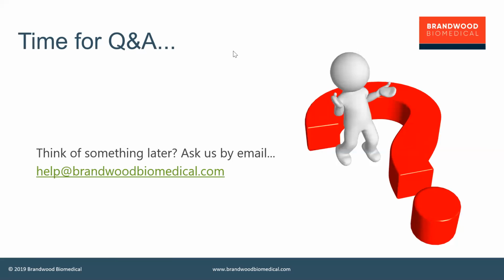We've got a question from Emmett. If you have a well-established product with historical complaint codes, should you correlate those with harms in the FMEA? Very good question. With historical, yes, I think you should. Undoubtedly. That's one of the things I was saying earlier, and it's not just FMEA. FMEA is part of risk management, and risk management is broader than that. When you're doing hazards analysis, when you're doing your risk analyses like FMEA, if you're at the beginning of a device development, often there's a fair bit of hypothetical in there. You're making estimates of likely failure rates. And a good way to validate those, at least the failure modes, is to look at the public post-market databases and the literature. Absolutely. See what other people have seen in terms of how devices fail and validate that.